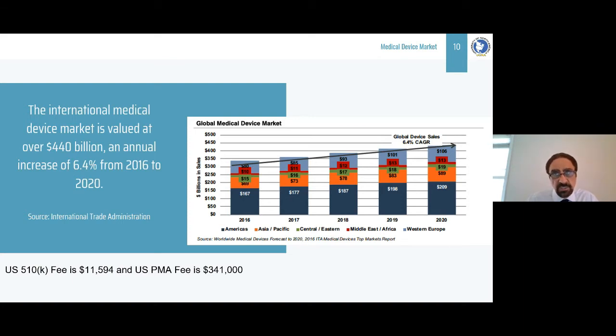So let's say, for example, you design a device and you decide to put it on the US market. This device has to be submitted to the US Food and Drug Administration, FDA. And they have an extensive procedure to evaluate this device. They evaluate the device in every aspect. They want to make sure it's safe as far as electrical safety and electromagnetic field compatibility. That means it has to be safe itself. It should not shock you. It should not cause any problem for the user or the patient. But also it should be safe against other devices. So if you are in an operating room and you have a medical device, and then there are other medical devices, your device should not cause signals that can affect the operation of other devices and interrupt the other device's operation.